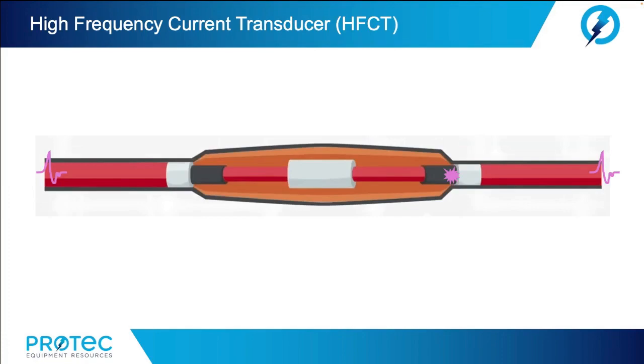These pulses will travel dozens of meters along the ground grid in the form of high-frequency current pulses in the range from 500 kilohertz to around 50 megahertz, usually centered near 10 megahertz. High-frequency current transformers are a reliable method to measure these high-frequency PD pulses. These pulses spread out onto the ground grid like ripples in water. They are especially useful for quickly detecting or testing for internal PD in a large area, such as an entire power transformer or an entire cable, or even an entire substation.